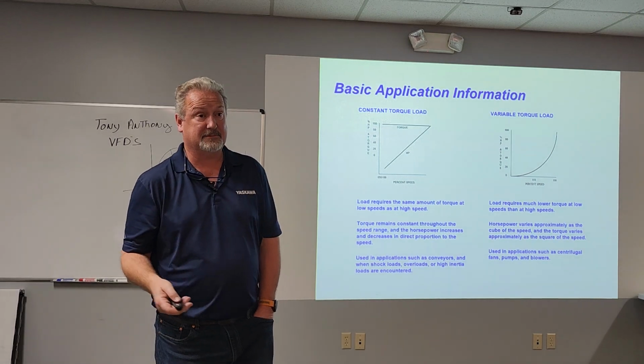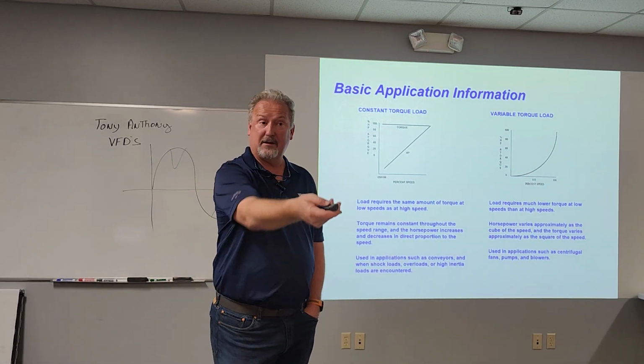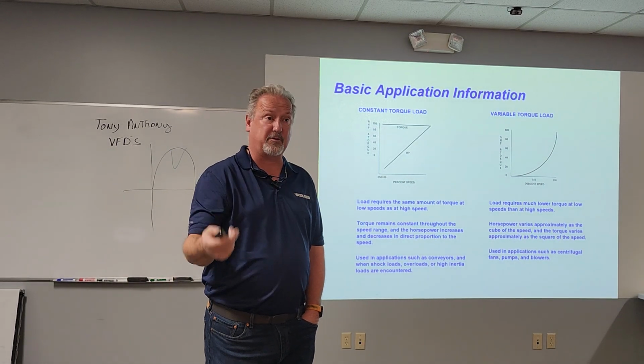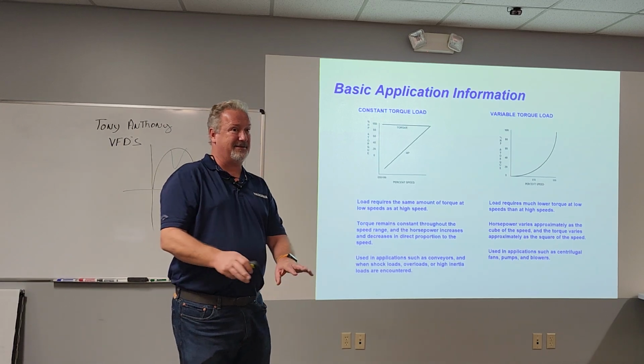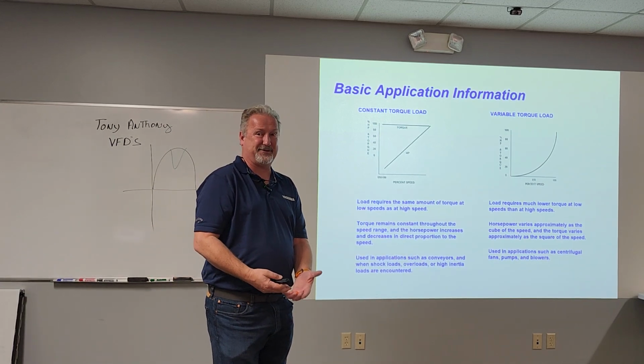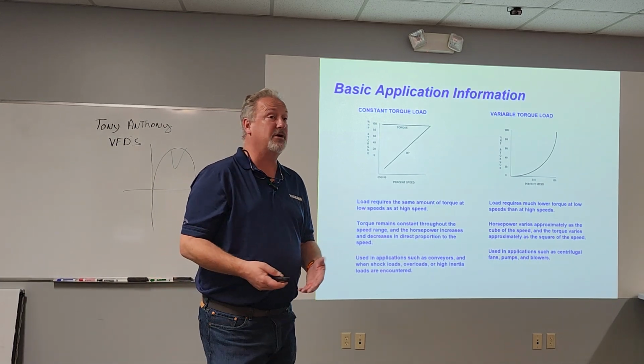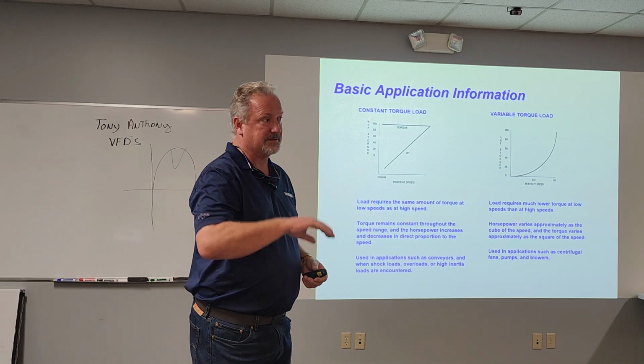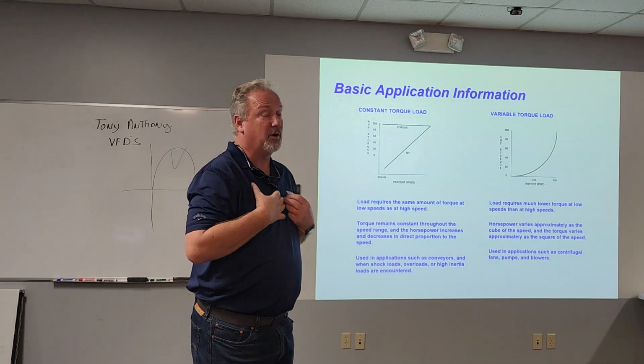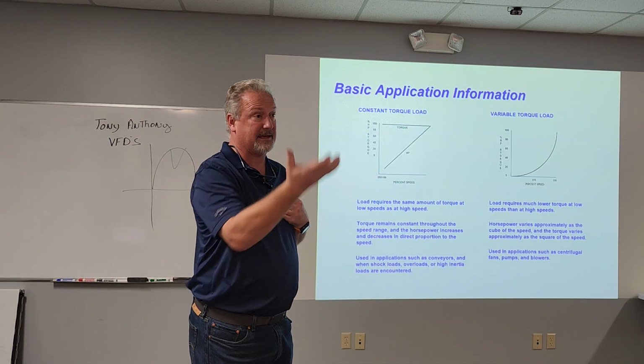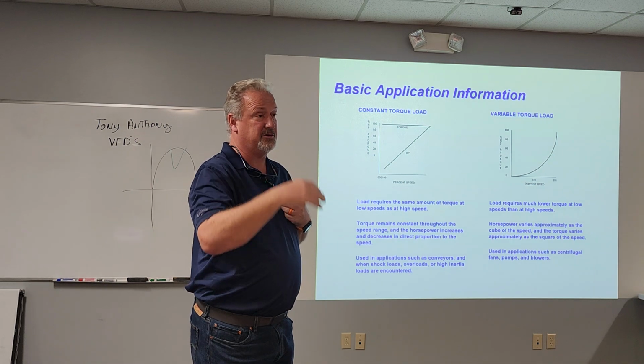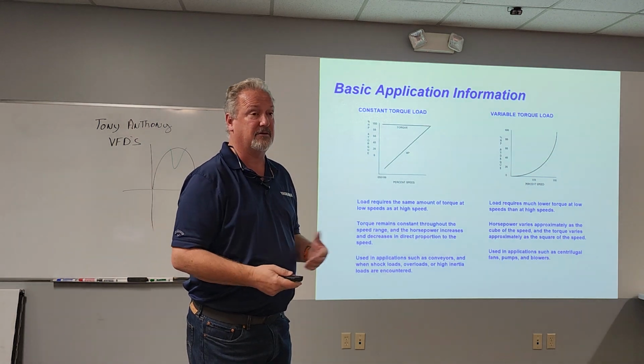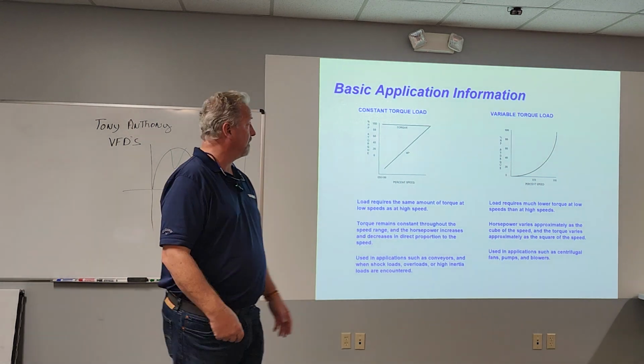People do it all the time for balancing reasons, for different things. Like what you're saying, people are trying to get more flow. Engineers slightly under-designed it and say, hey, can you give me 10% more? There are a lot of reasons we do it, but you've got to be careful, because one, the drive has to be sized big enough to take that extra current, and two, at some point you can't go too high.